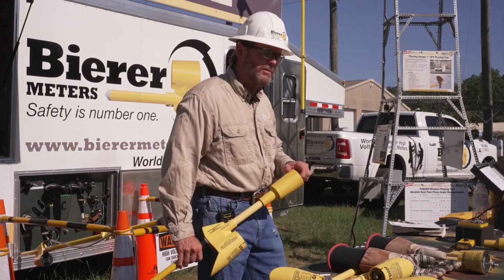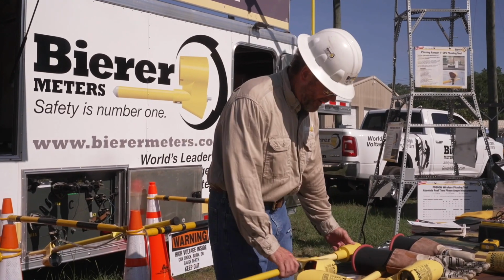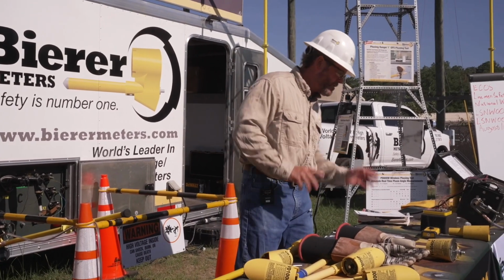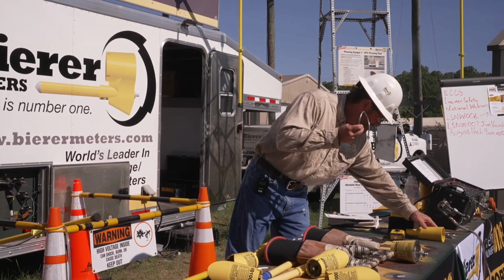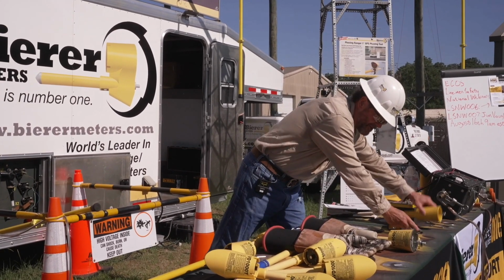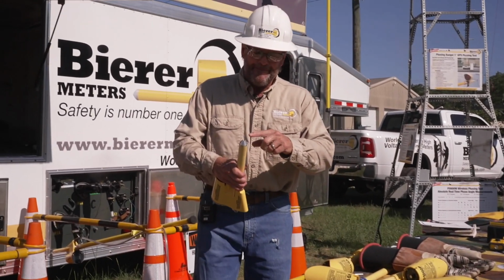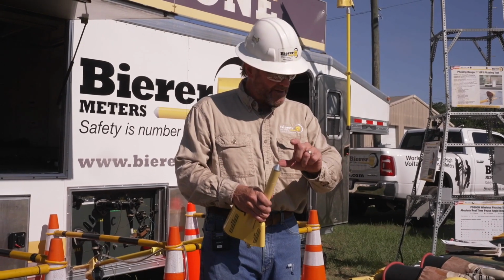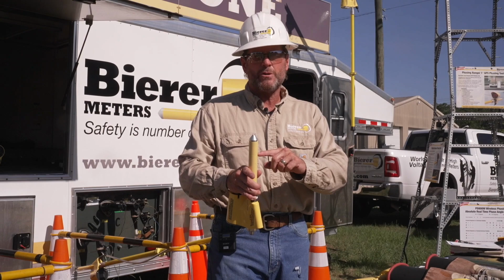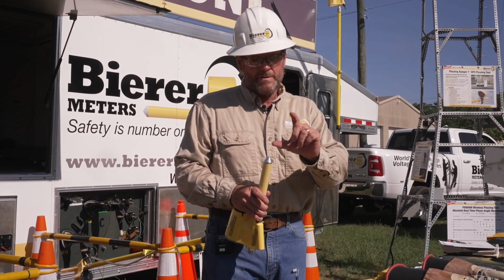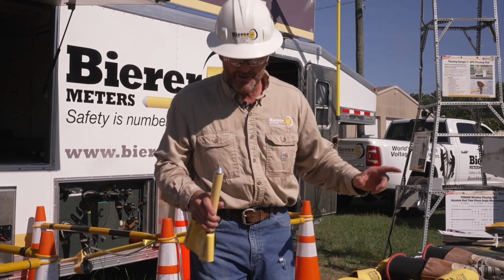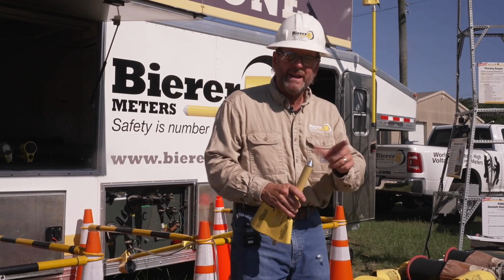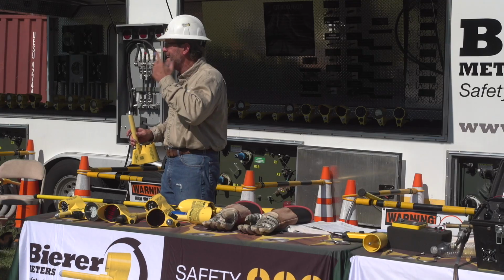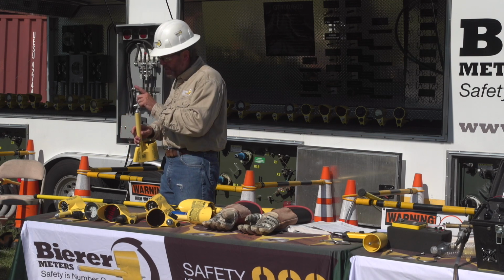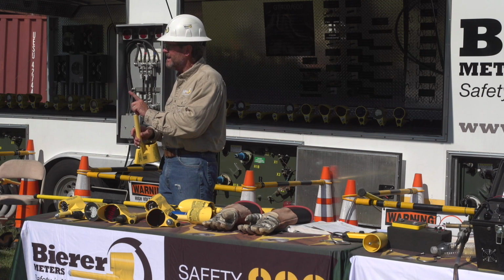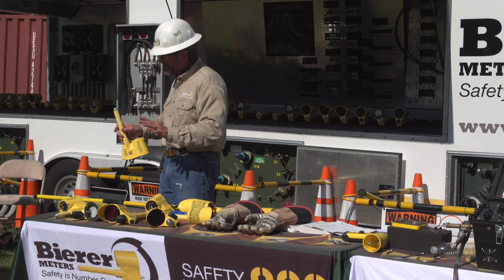It's also very important, let's make a note - when you're using your device, your phasing tool, voltage indicator, wireless or corded, you always want to use the proper accessory. You're going to use a straight probe, hook probe, or bushing adapter. The reason is you don't want to take the shortcut of not using it, because the opportunity to bypass that line limit Ryan was talking about is much greater. Always use the proper accessory. A lot of guys lose their straight probe or hook probe, and before you know it they're not using it anymore, or they just forget, or it becomes habit and they don't even think about the safety aspect. But you always want to use the proper accessory on the end of your cone tip or device, regardless of manufacturer, okay?